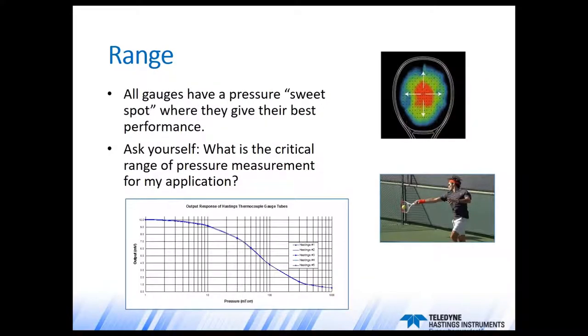Just like a tennis racket has a sweet spot, vacuum gauges have a pressure sweet spot where they will give their best performance. In the graph shown, a thermal conductivity gauge has about a three-order-of-magnitude sweet spot. Different techniques have different pressure regions where they work best. You probably can run a hot filament ionization gauge at pressures above 1×10⁻⁴ Torr, but that's not operating in the sweet spot. Ideally you want to stay well within the operating range. So ask yourself: what is the critical range of pressure measurement for the application?